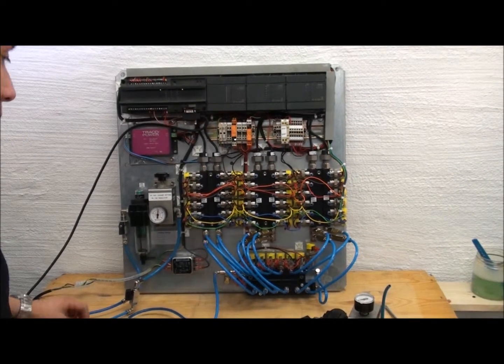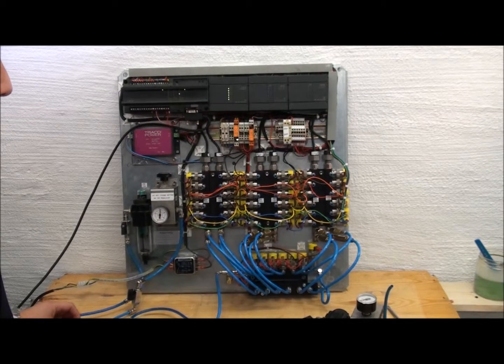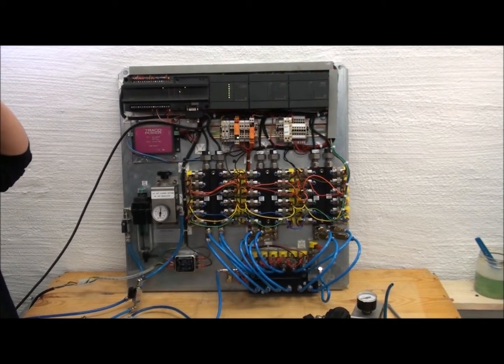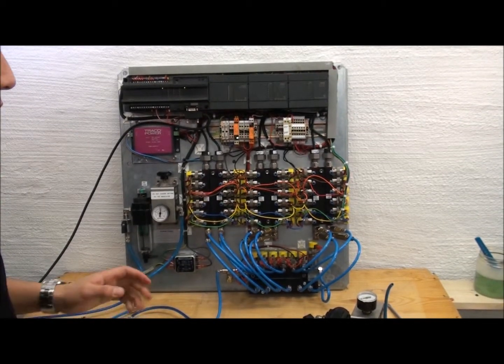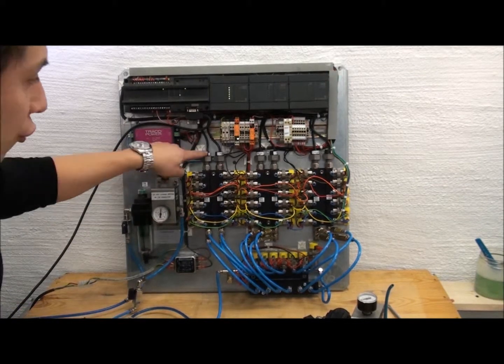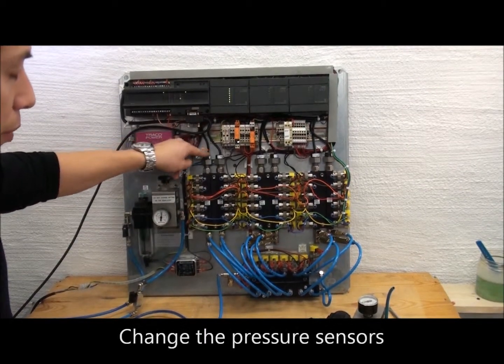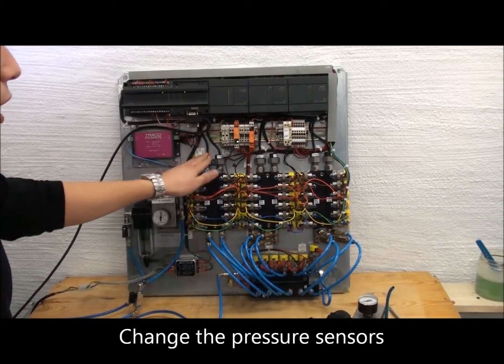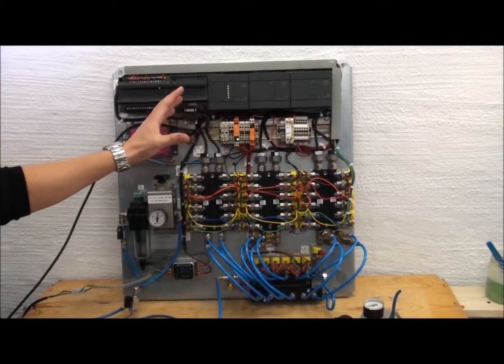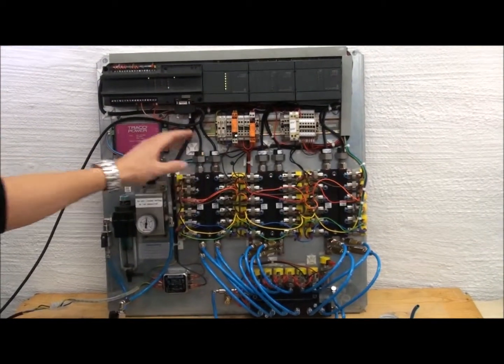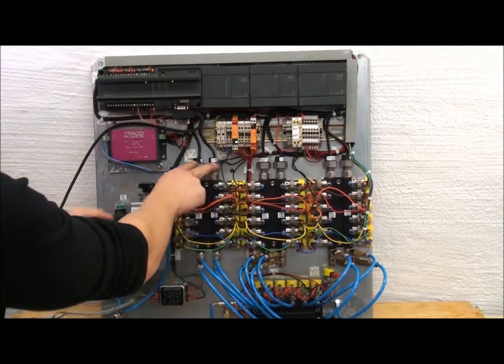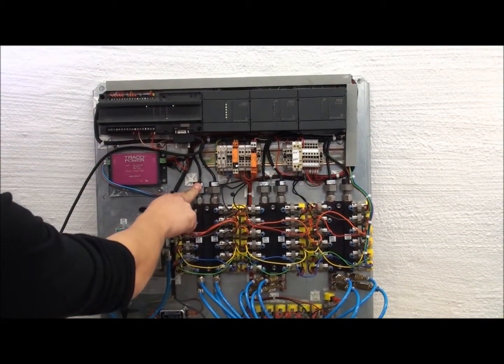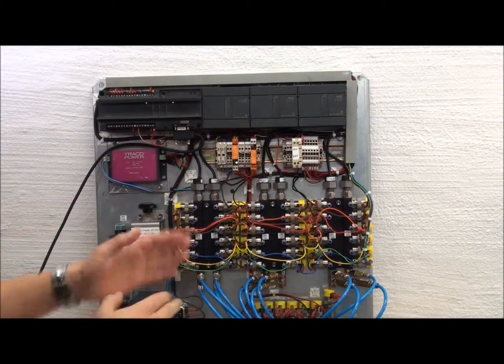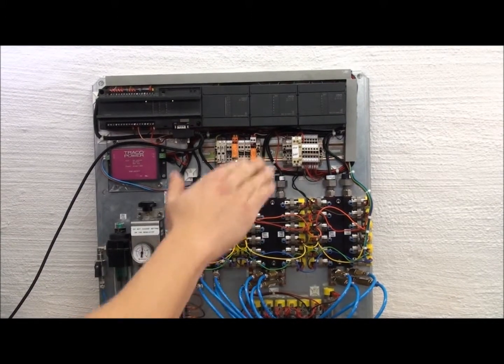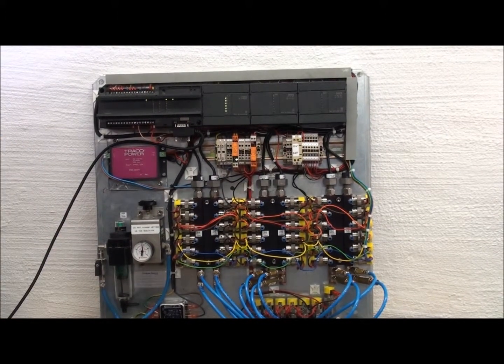The last step, and the most important one as well, is to calibrate the system. You need to calibrate the system when you change the pressure sensor, because they are all different. And when you calibrate the system, what you do is to explain to the PLC that the new values from the pressure sensor are equivalent to certain levels. So that's what you do when you calibrate the system, actually.